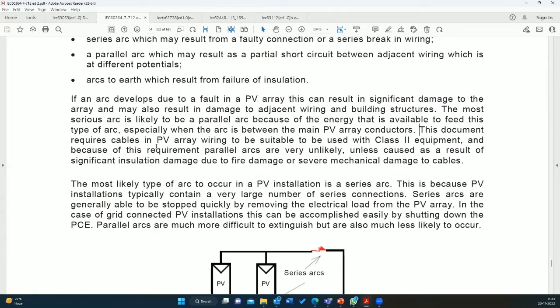So this document requires cable in PV array wiring to be suitable for use with class 2 equipment. You read here, I am just highlighting: this document requires cable in PV array wiring to be suitable to be used with class 2 equipment, and because of this requirement, parallel arcs are very unlikely.